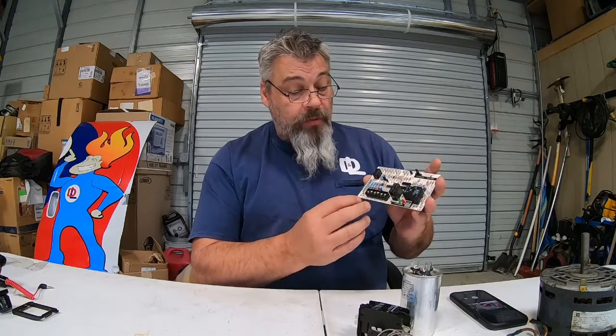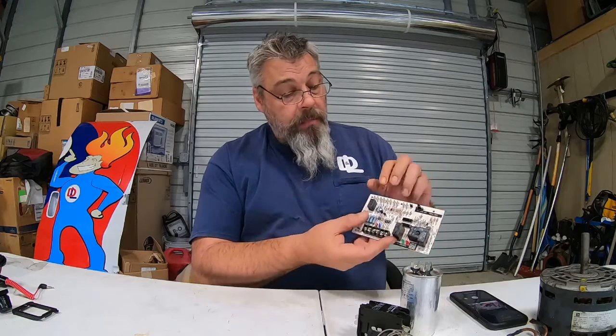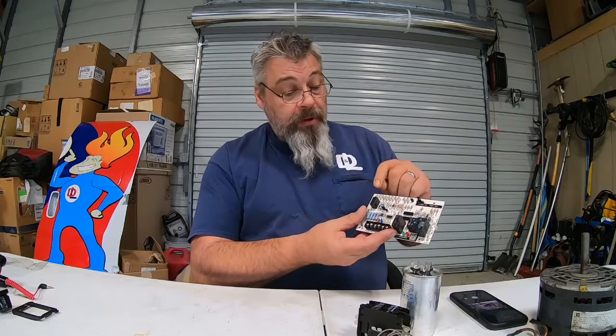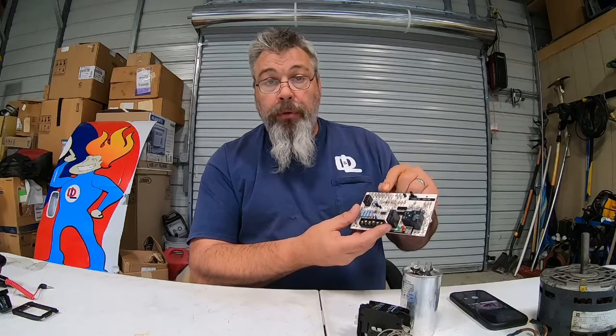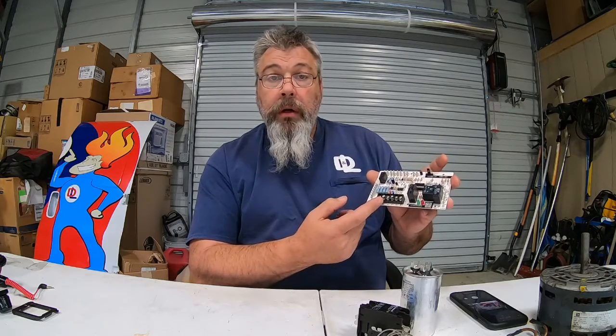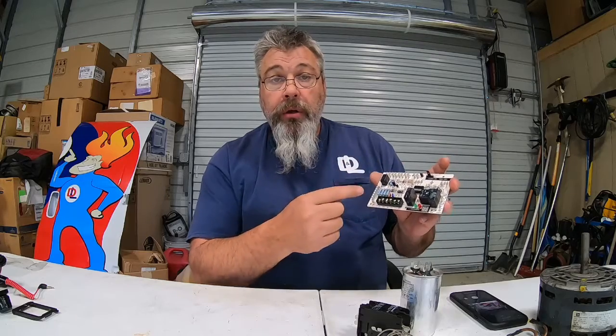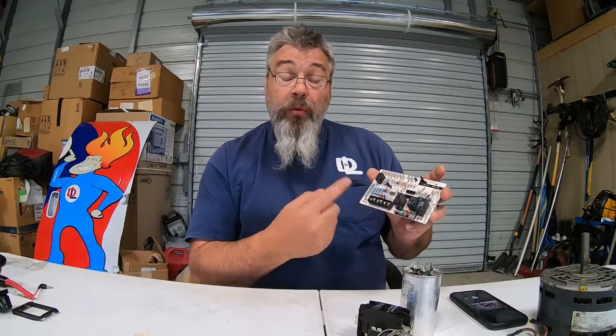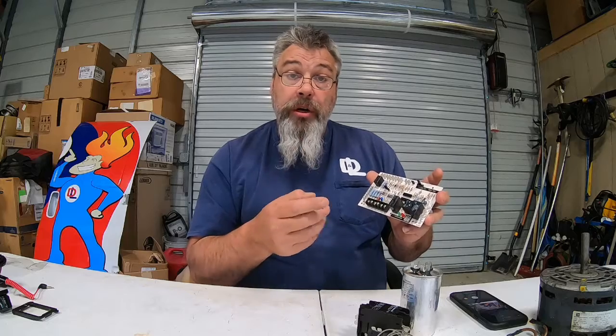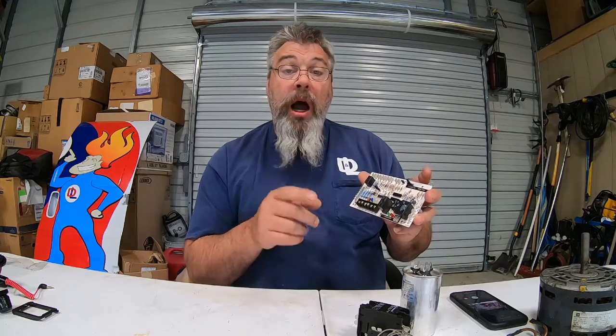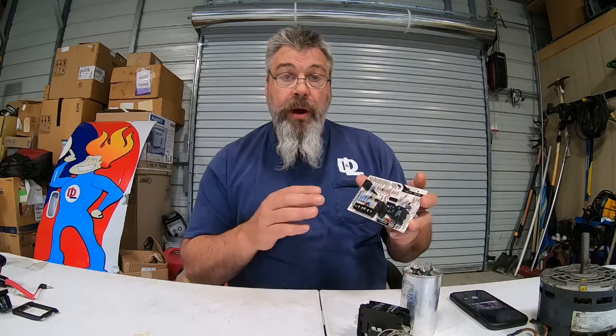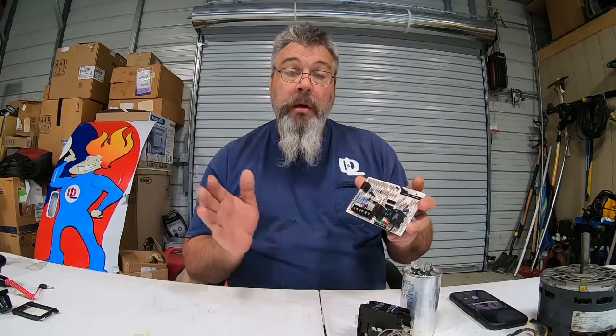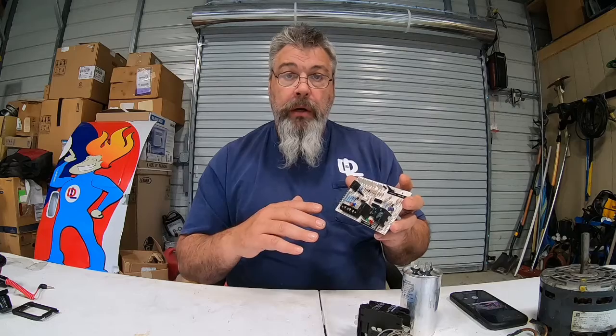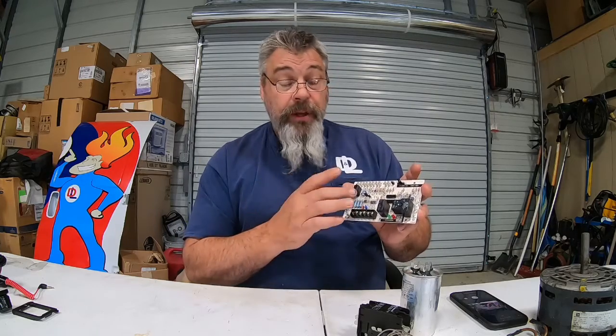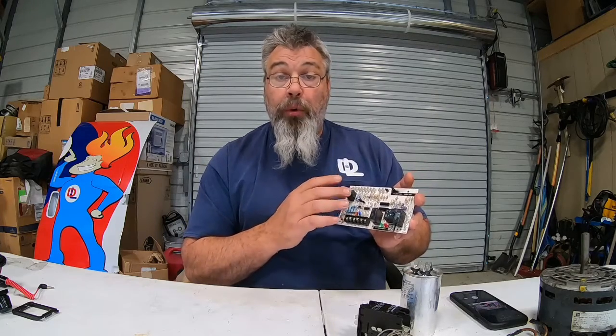What we have is power comes in from our thermostat, power goes out to our unit. These terminals on the top here are labeled almost the same as the ones at the bottom. The only difference is we have to run through the board. So we have to run through our safety switches. We have to make sure our low pressure is met. We have to make sure that our high pressure is not met. So we have to make sure our low pressure is above where it's supposed to be and our high pressure is below where it's supposed to be. If the high pressure is above that, it's a safety lockout. The board will lock it out, so your unit will not run.